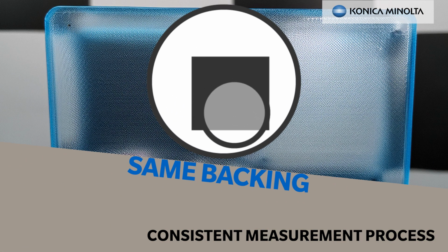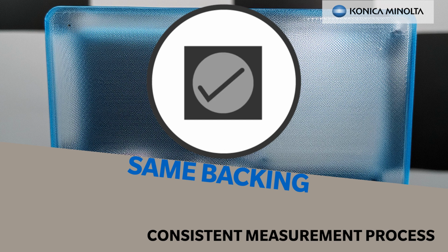You should also always measure with the same backing, as many samples which appear opaque aren't 100% opaque, and using a different material underneath can therefore impact the measured data. The same is also true for picking up the sample to measure. Not only does it make sample positioning and consistent contact with the sample more difficult, but it can introduce backing errors.